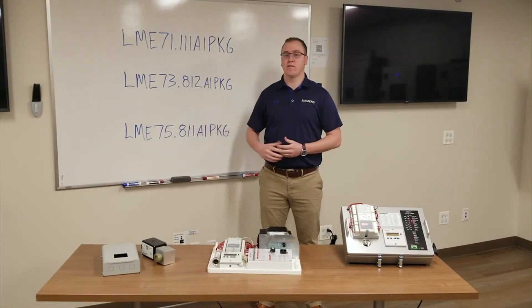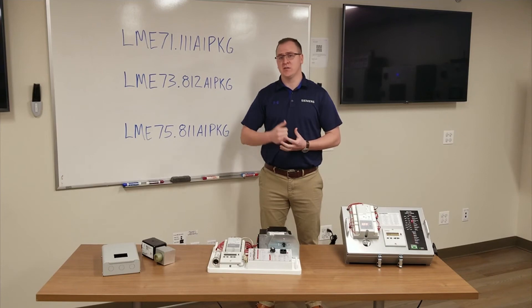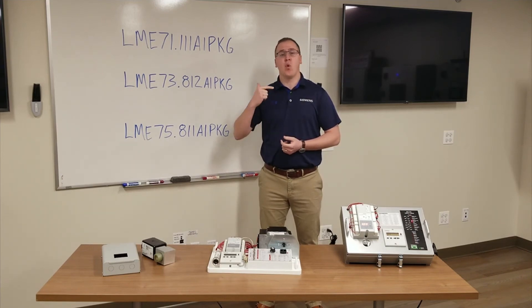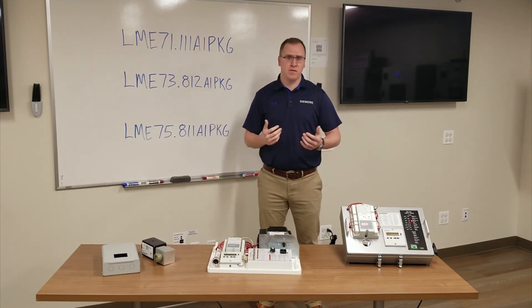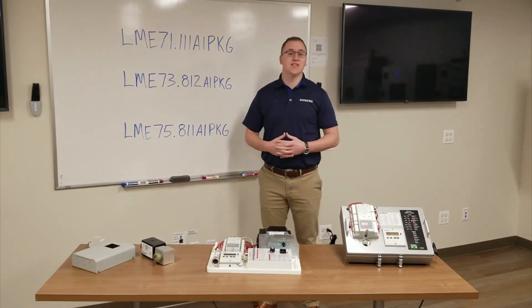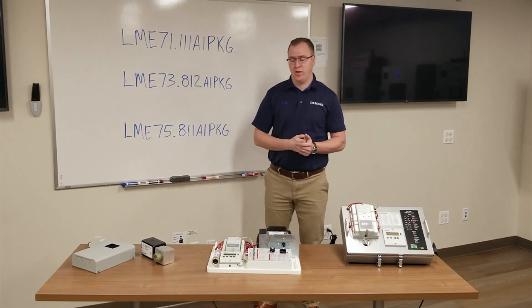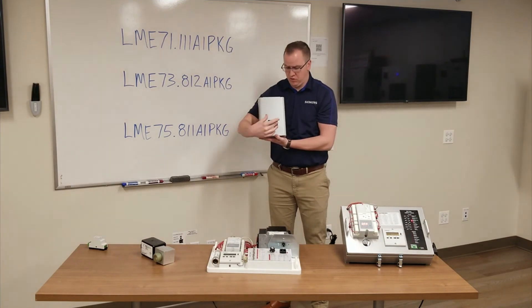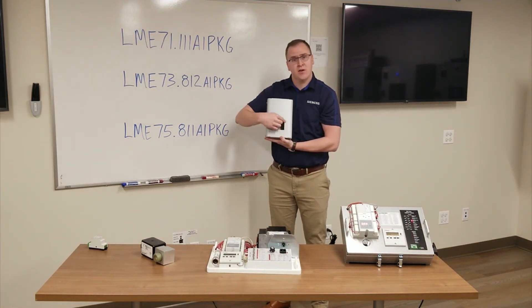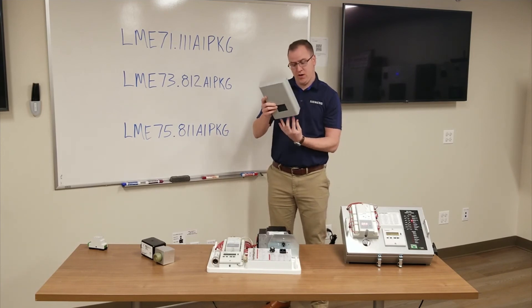These three versions will cover the majority of applications. There are other versions available, such as a no-purge version, versions that require valve proving, or applications that require a PWM blower — these aren't listed here but can be found in our literature. The LME7 is designed to be in a control panel, but when that isn't possible, we've developed a NEMA 1 enclosure for the LME7. It has a knockout so you can still see the built-in display, as well as conduit connections for wiring coming in from the bottom or on top.